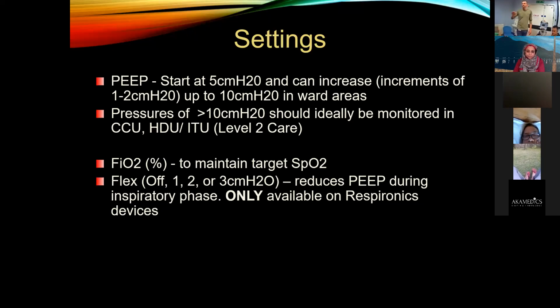Okay, so for example, if you have got your PEEP set at 10 and you have your Flex set at 3, the PEEP will be delivered at 7 until the very end of the patient's expiratory phase, when it will ramp up to 10. And then when your patient starts their inspiratory phase, it will drop down to 7 and then up to 10 and then down to 7 and up to 10. Why is this important? If you've got a patient that's struggling to tolerate high levels of PEEP, you can try to use a Flex option. Okay, it might make it a little bit more comfortable for them.